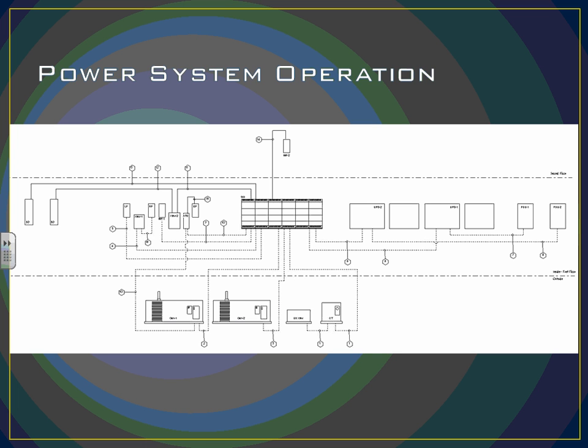I think, and I know you talked about this, the fact that those gensets feed into your switch gear and then the utility feeds into switch gear, so you're using breaker pairs. Yes. To switch load, because those gensets will pick up 100% of the building, correct? Yeah. Okay. That's kind of what I was looking for. And your parallel gear must be part of that. Yes. The parallel gear for the switch gear, and that acts as the breaker for it as well.